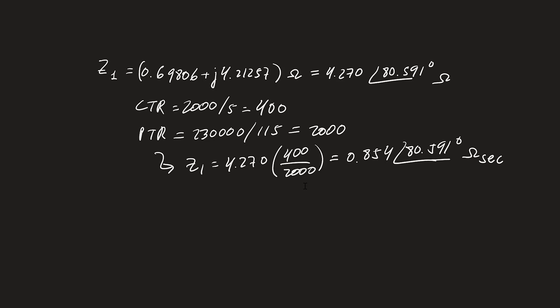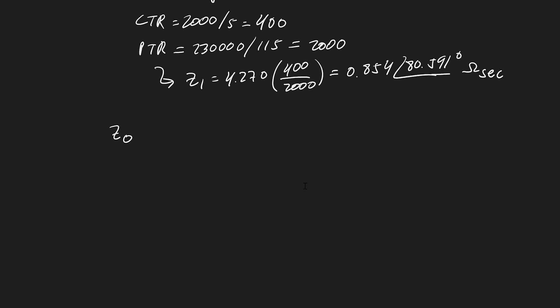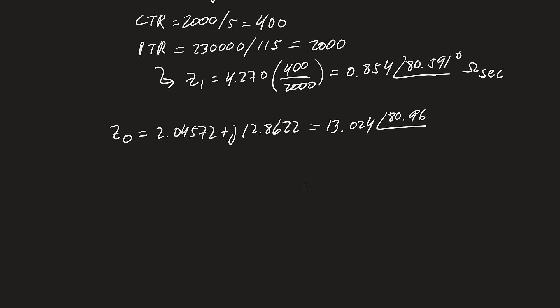We can do the same for the zero sequence impedance, which we'll need for the zero sequence compensation factor. Z0 is 2.04572 + j12.8622 ohms, which converts to polar form as 13.024 at an angle of 80.963 degrees in primary ohms. Converting to secondary terms by multiplying by CT ratio and dividing by PT ratio gives 2.605 at an angle of 80.963 degrees in secondary ohms.